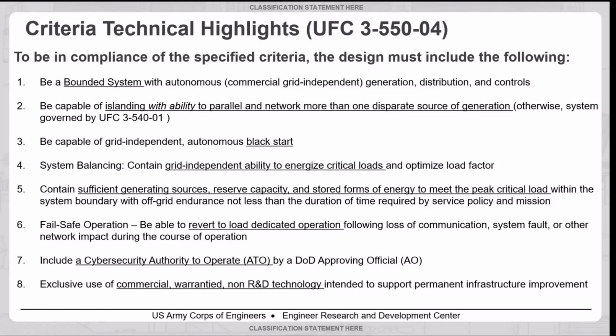We have to have sufficient generation to meet the peak critical load within that bounded system, and it has to be able to support the critical load within its boundary for that duration as required by service policy. So for the Army, that's 14 days.